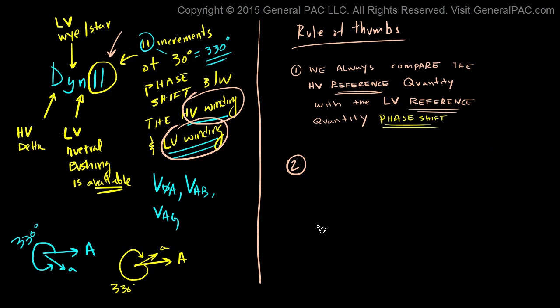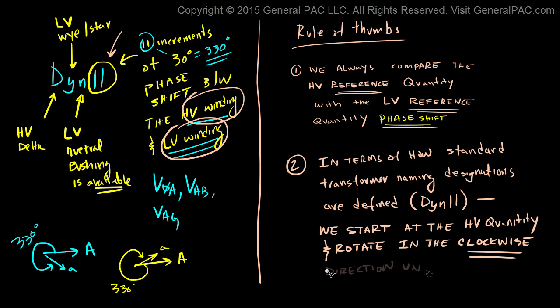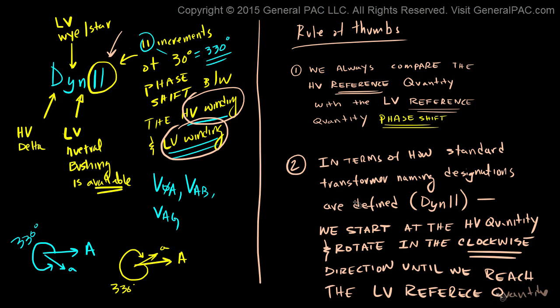The second rule of thumb is that in terms of how standard transformer name designations work — we're talking about how the dyn11 designation is defined — we start at the high voltage quantity and rotate in the clockwise direction until we reach the low voltage reference quantity.